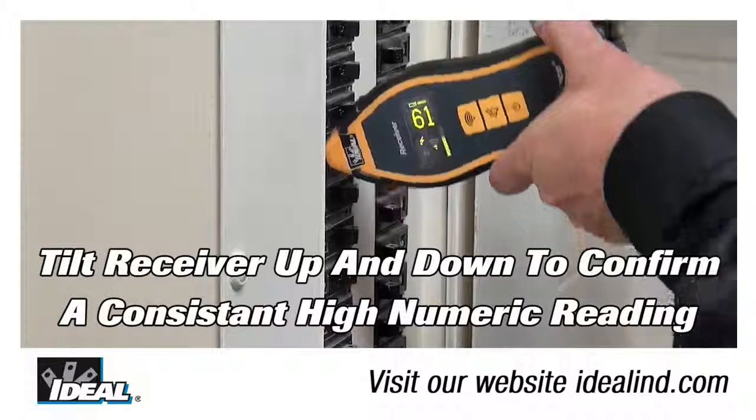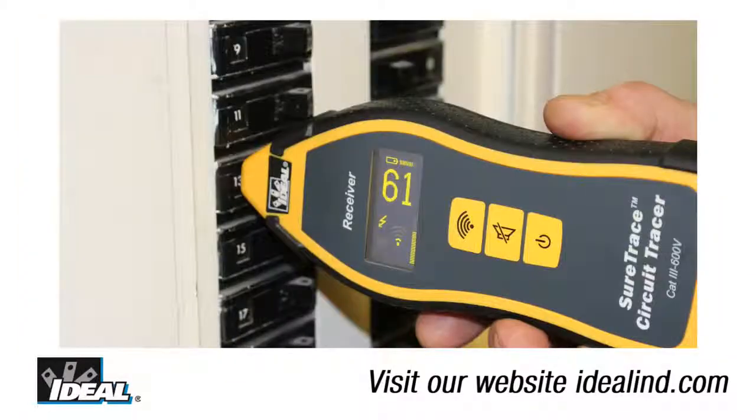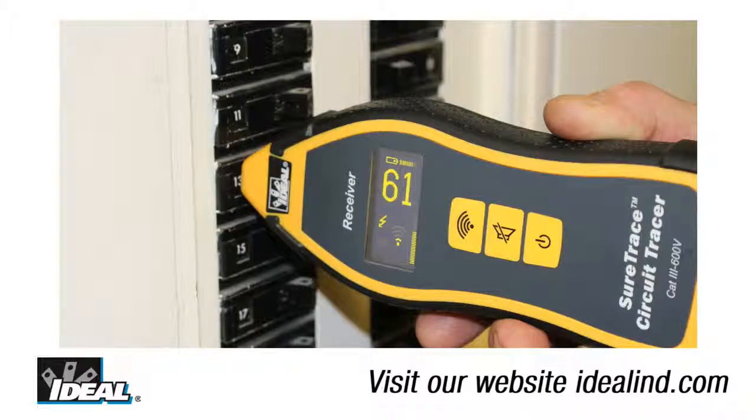To double check your findings, tilt the receiver up and down by 45 degrees. The readings should remain fairly stable. If they do not, then this may not be the correct breaker. Be sure that the nose of the receiver is centered on the conductor located under the panel cover. The nose should also be on the outer edge of the breaker.